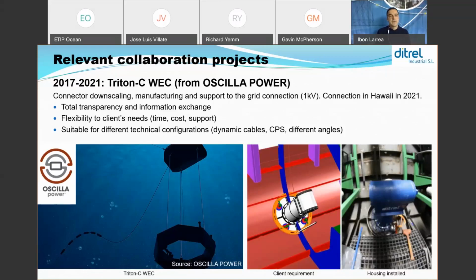We're also flexible from the technical point of view, making the connector suitable for different configurations, like different dynamic cables, steel armored or synthetic armored, different cable protection solutions, different sizes of bend stiffeners, and even different angles of connection. We can see in the left picture the floater with the dynamic cable.